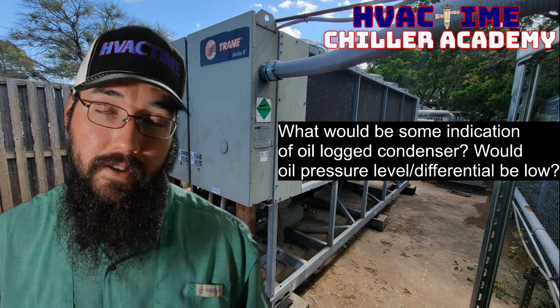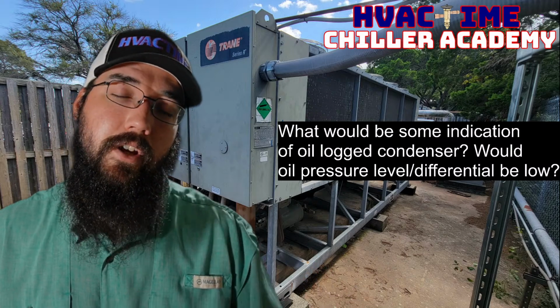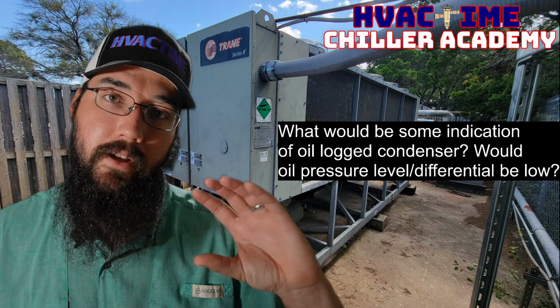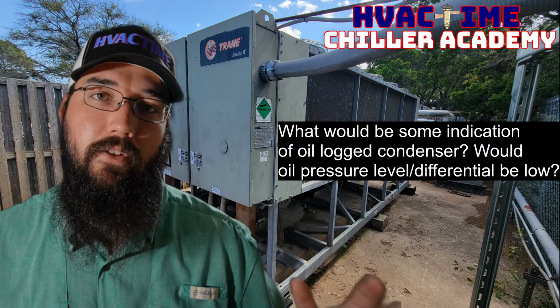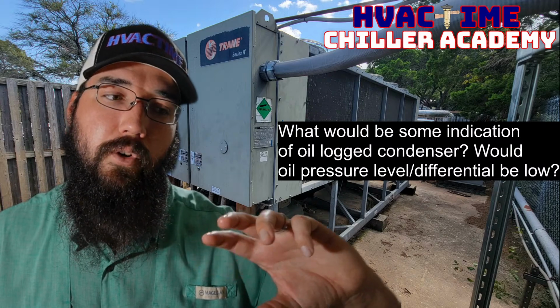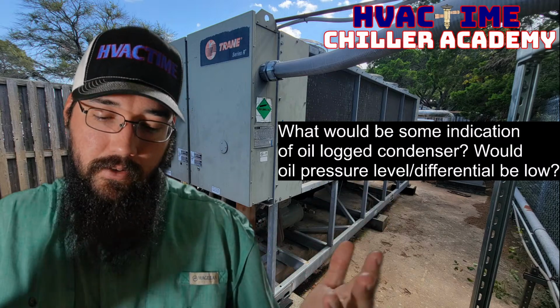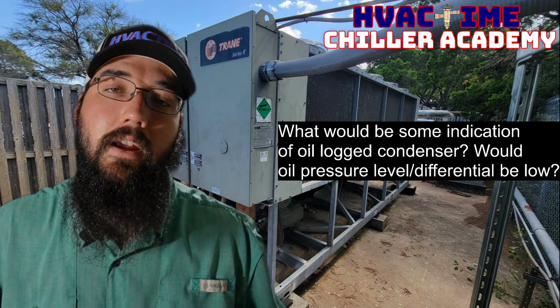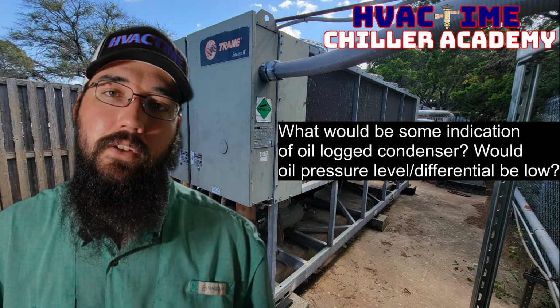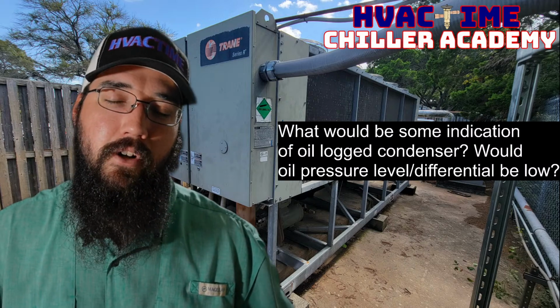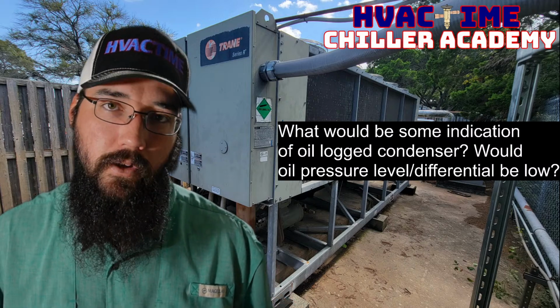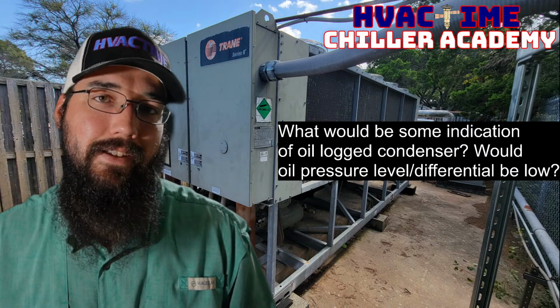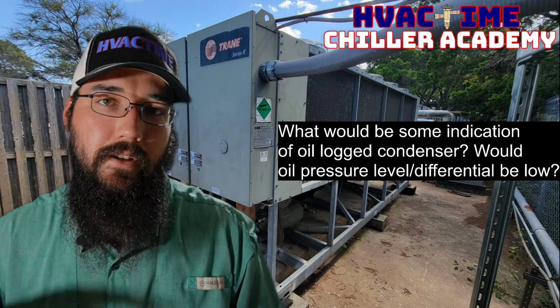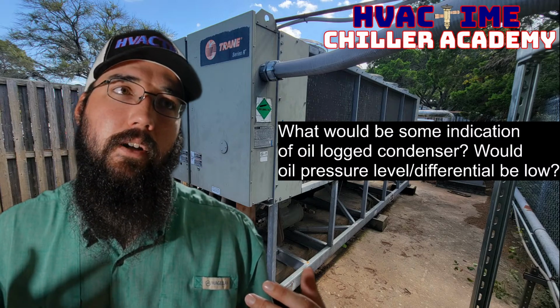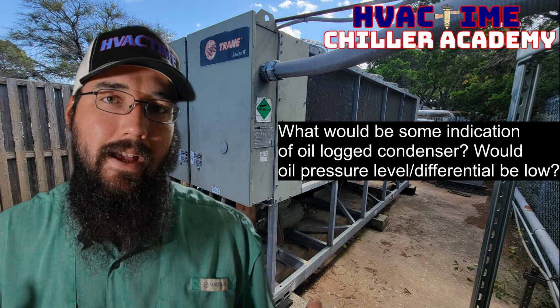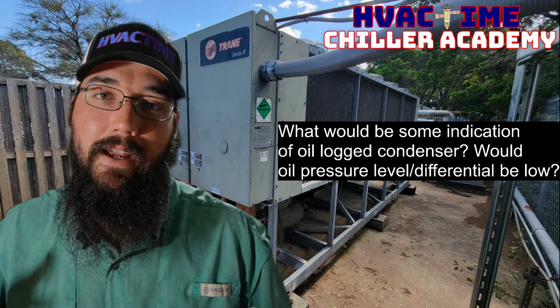Whereas with the evaporator, typically we're either injecting the refrigerant in from the bottom and pulling gas off the top, or even if we have a falling film, we're injecting it into a spray rail, and then the refrigerant falls to the bottom, including the oil, and we're still pulling gas off the top. So either way, the evaporator becomes a natural trap for our oil that the condenser naturally isn't, because in the condenser we have the ability to gravity drain the refrigerant out. Now this is true for flooded and falling film.